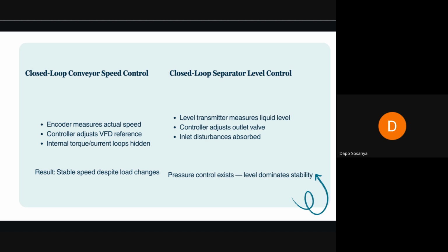The internal torque and current loops are hidden. And the result is you have stable speed despite load changes. So whether the conveyor is carrying 1 ton of materials or 20 kg of materials, you will see the speed will be stable. Without that encoder making measurements and without the VFD giving reference to the motor, the process will be like a human running uphill.